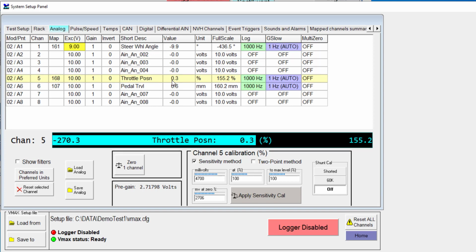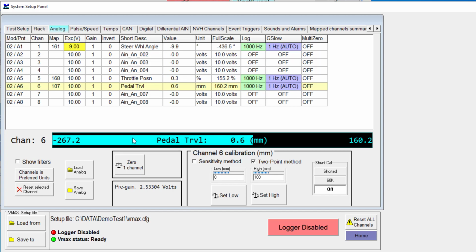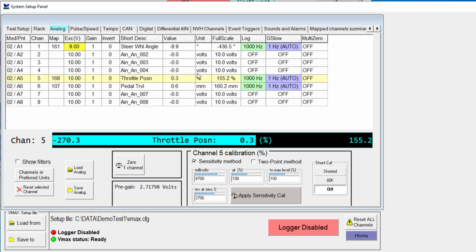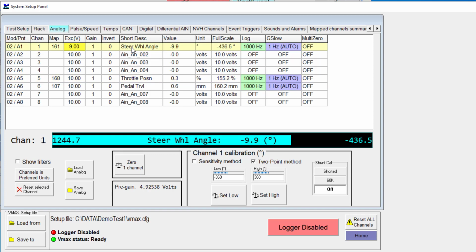So something else I wanted to illustrate, if you need to, like before each event that you capture, make sure that everything is completely zeroed out so that you've got really clean data, you can do that on an individual channel by channel basis like I showed before. Hit 0 on one channel, hit 0 on another channel here. Alternatively, and especially if you have a lot of channels that you need to zero, this could be very beneficial.